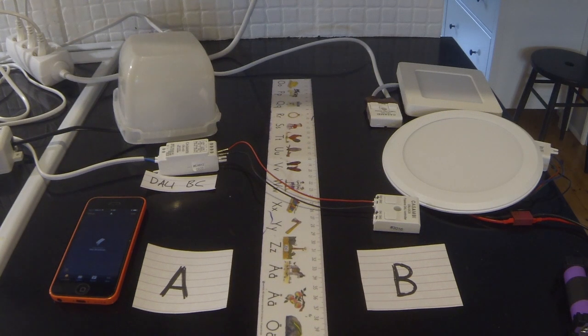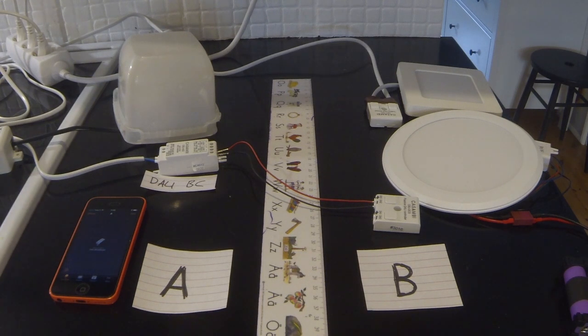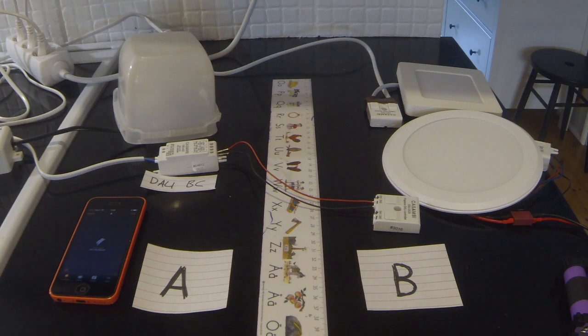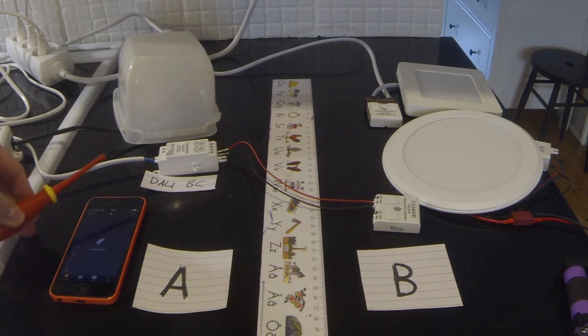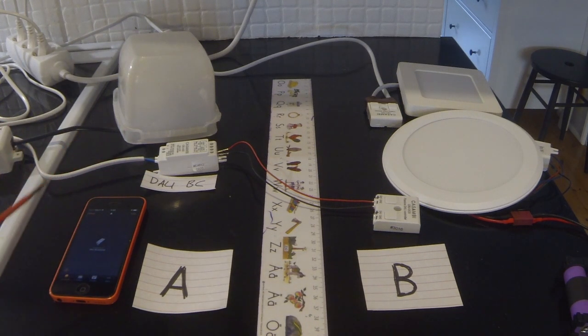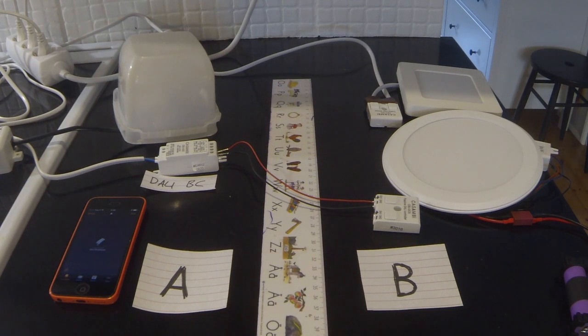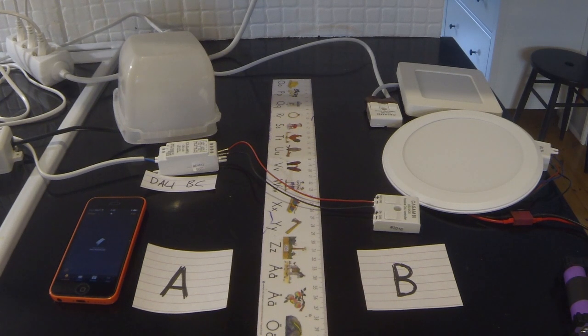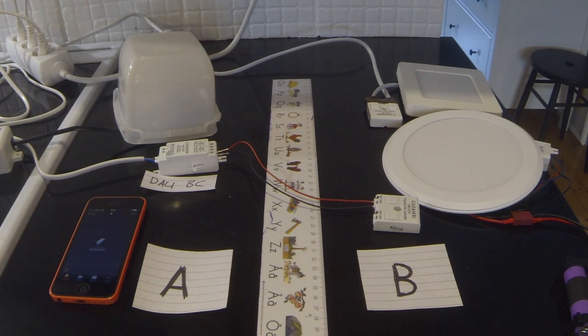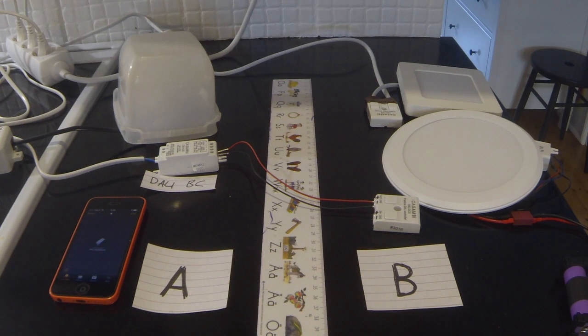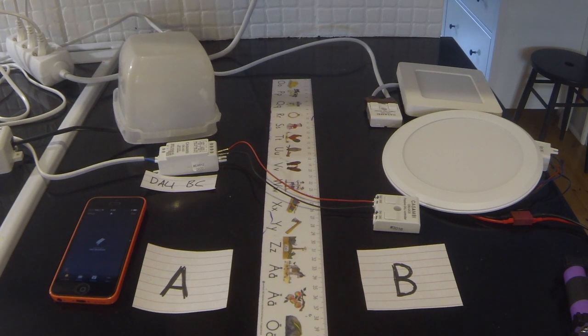So for example, the command coming down these wires could be dim the lights to 80%. And all of the lights that receive that command, which theoretically should be all of them, would then be expected to dim to 80%. Realistically, the closest any of you are going to come to DALI is if you have a DALI LED driver which is powering your lights. And even then, they're going to be stuck in your ceiling somewhere and your electrician will probably put them there for you. DALI is predominantly used in large commercial buildings, things like offices, warehouses, museums, things like that.